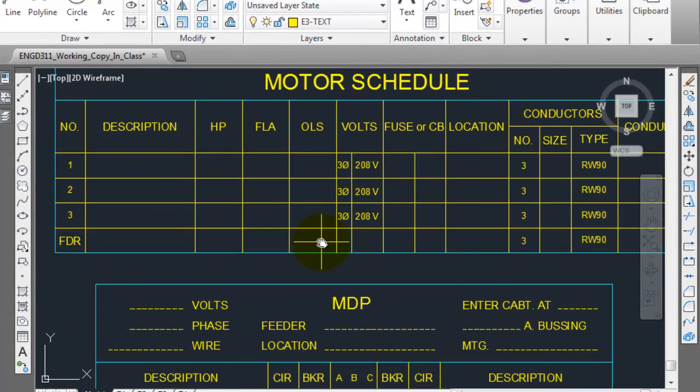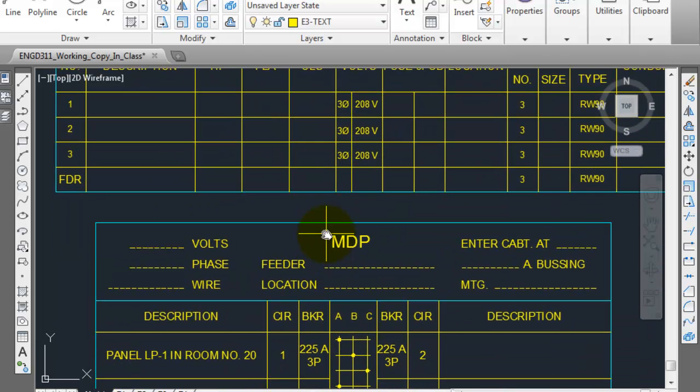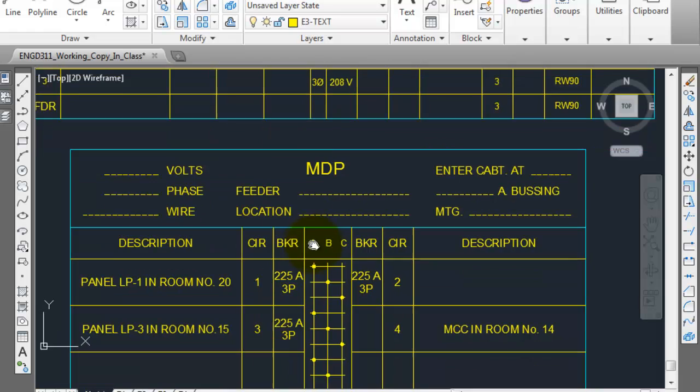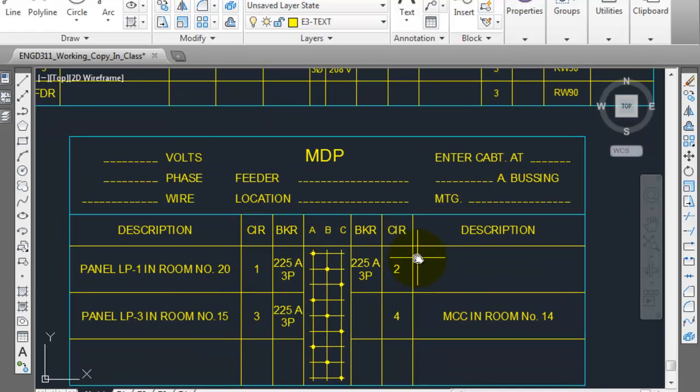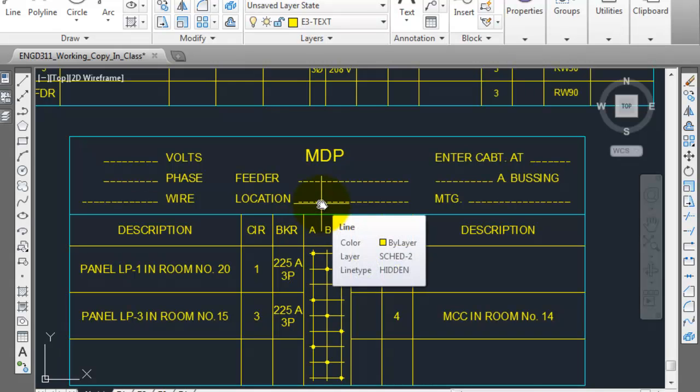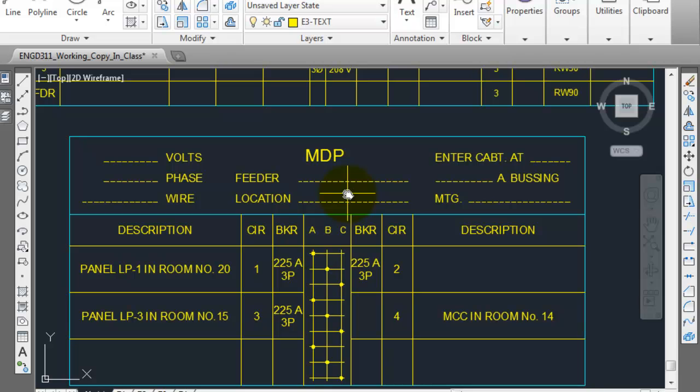You're going to add all those up, and then you're going to look in table number 2, and you're going to find an appropriate feeder size for that number of amps. So let's say, for example, we add up 175, 175, 175, and let's just imagine that our motor control center takes 100. I'm just using an example. It's 625 amps. So we're going to look in table number 2, and we're going to use a 1250 kilo circular mill American wire, kilo circular mill size wire. So if you look in table number 2, that's capable of 645 amps. Okay, this is just an example.